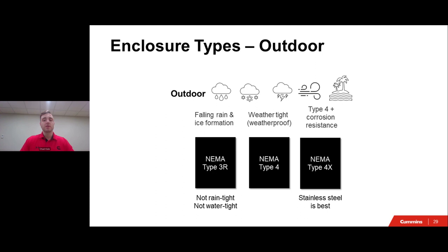Please note that these enclosures are not rain tight, which means that in the case of hard rain or any kind of pressurized water or oil, there could be water leaking into the enclosure. The 3R does not have those gasketed surfaces, meaning if subjected once again to a stream of water that is pressurized or really hard, that water could enter into your enclosure and cause damage to the internal components of your transfer switch. In the middle there, we have the Type 4 as specified by NEMA.